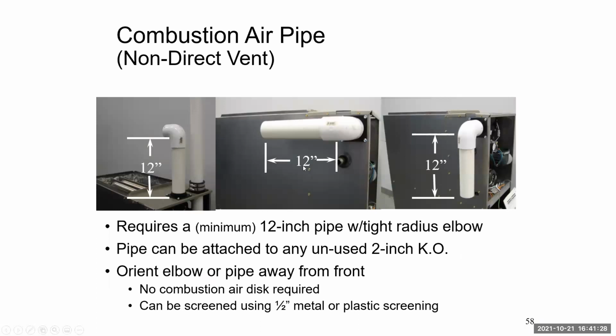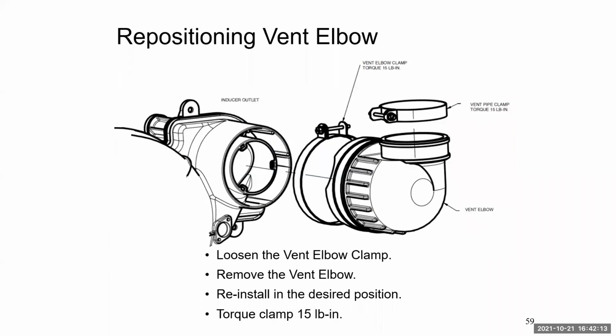If you have a system that can use fresh air out of the structure and not have to be piped all the way outside, you are required to have at least a 12-inch standoff, however you're piping that in. Read your manuals, because not every system accepts this. Most of your modulatings, you have to go outside together, and you have to be in the same pressure zone. One pipe can't go out the right side of the house, one pipe go out the left side. They have to be in the same exact pressure zone, or you will have pressure switch problems. I'm kind of showing you how that boot comes off and you can reposition it.